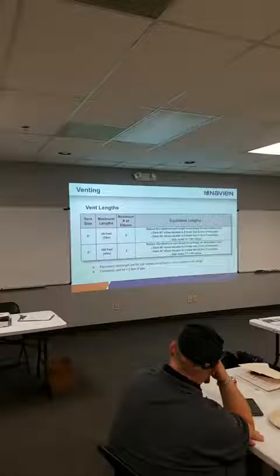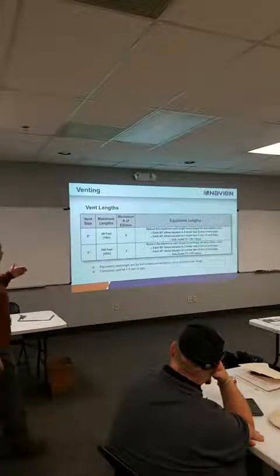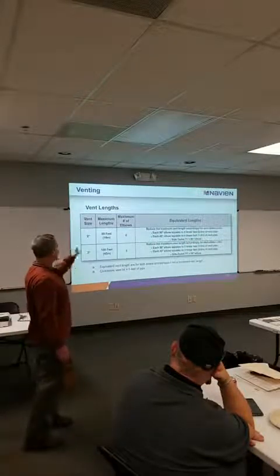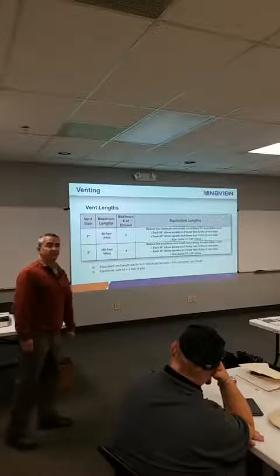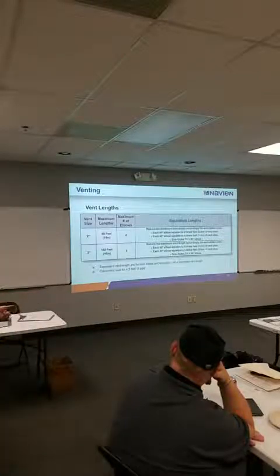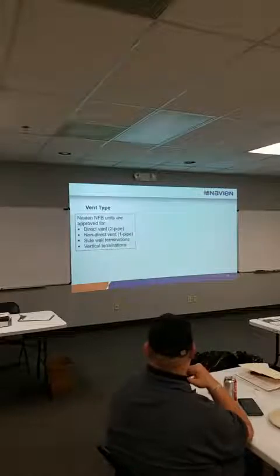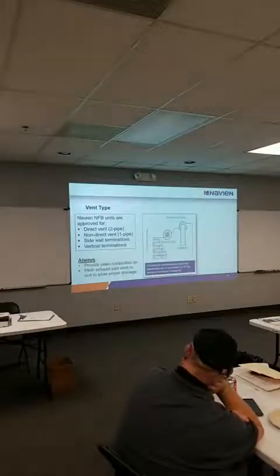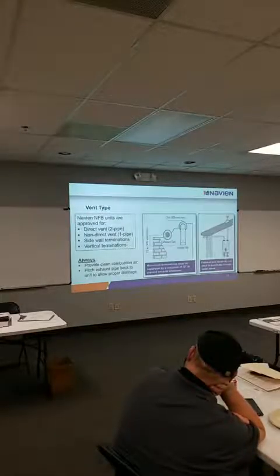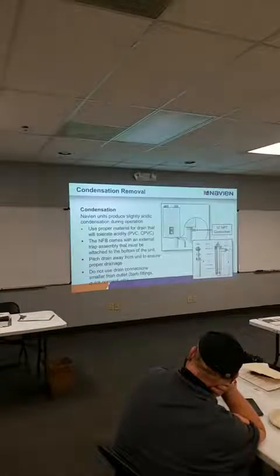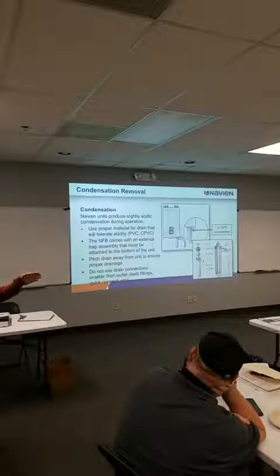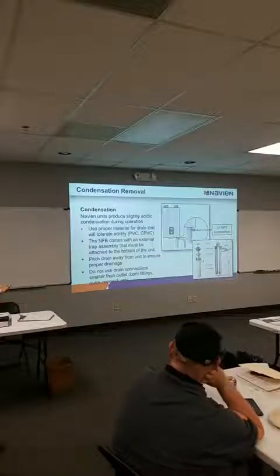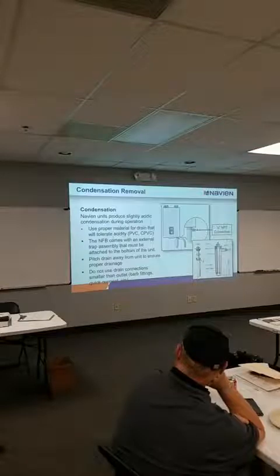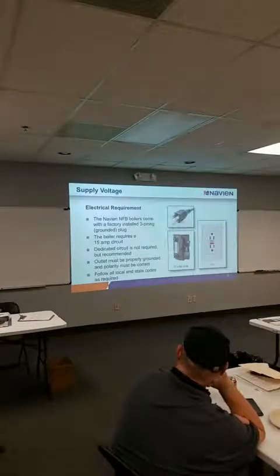So the venting, this is an old chart, because we're gonna upgrade it next month, where we're gonna take the 2-inch out to 65 feet. All the other rules are the same. So same venting pictures, again, it's all gonna look pretty familiar. This is the condensate trap that comes in the box, so it's a little goofy little thing, but it's easy to use, it's easy to service if you need to, and it hangs right off the bottom of the unit. Again, plug it into the wall.